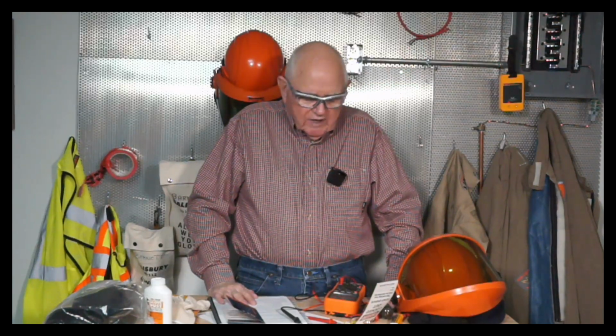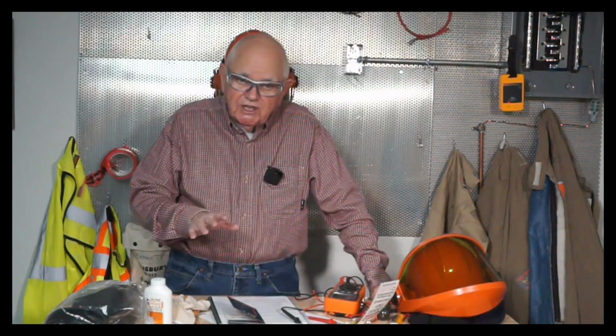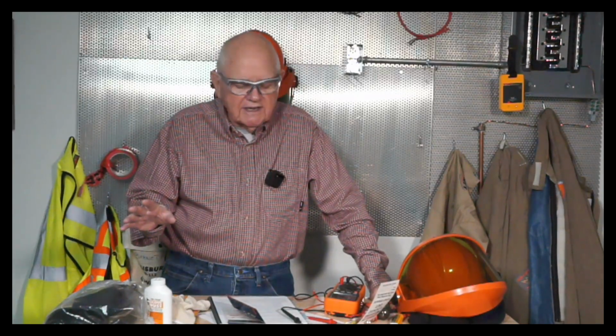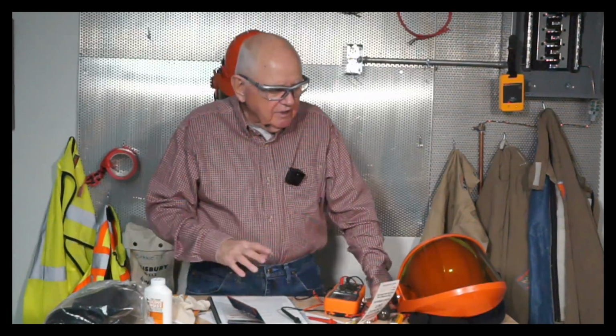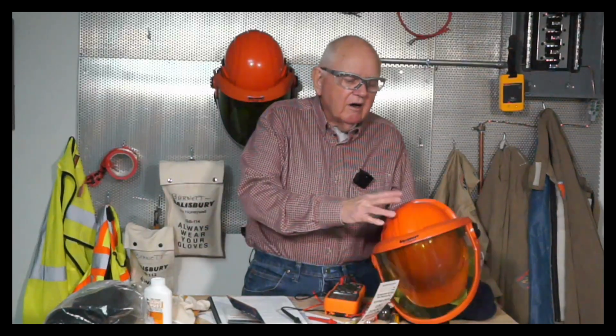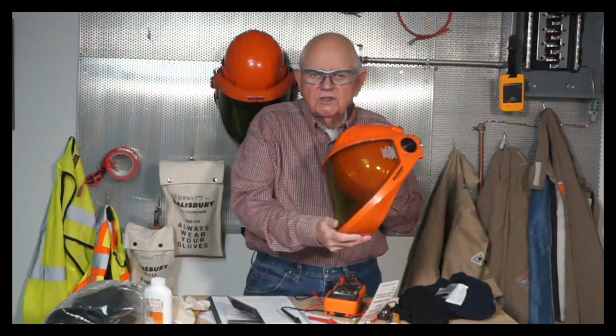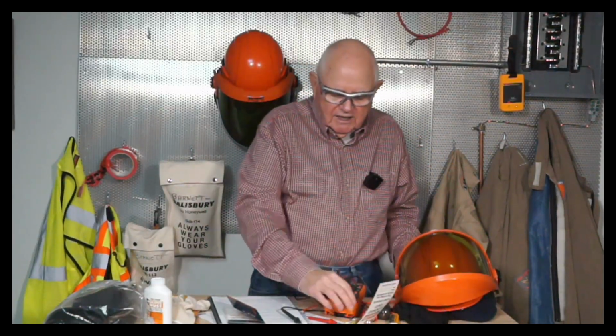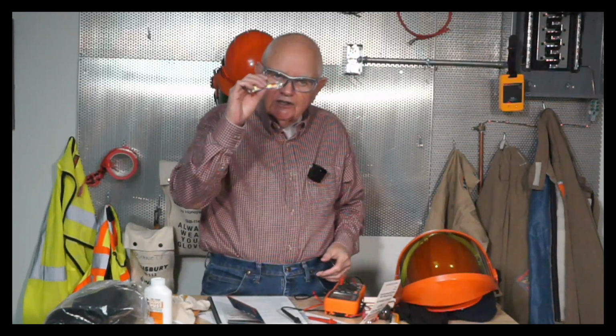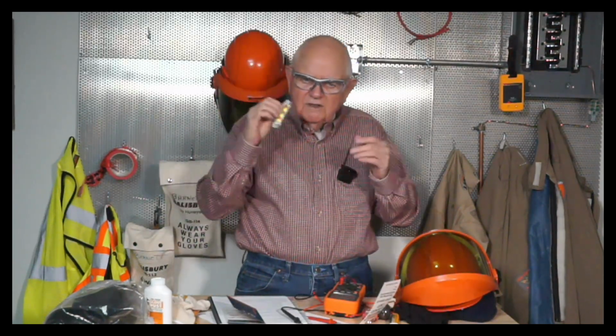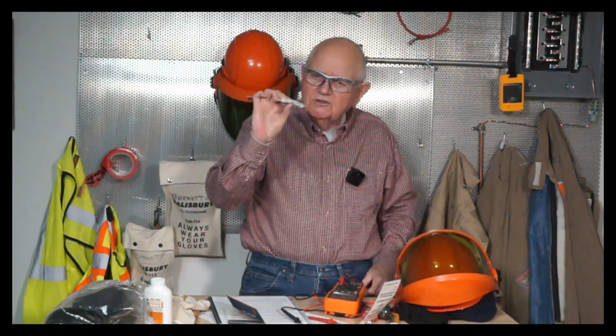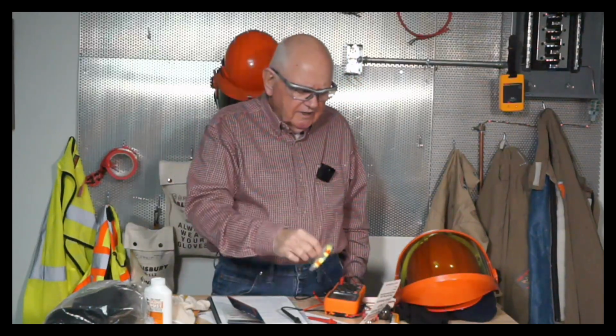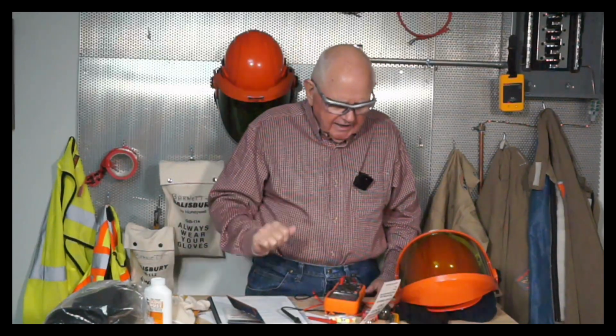Well, I'm going to wear my PPE based on 130.5G, whatever's in your policy, or once again, if I'm using that PPE category method. The things that I'm going to be required to wear: a hard hat, probably the face shield for arc flash protection. I need some ear canal inserts. There is a provision for ear muffs now, but I really haven't seen them used so far. And so we use our ear canal inserts. And safety glasses always under the face shields.